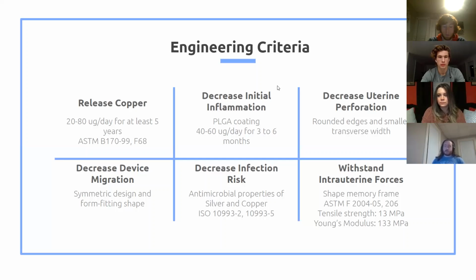So there are 6 main criteria that our device must meet. It must release copper at a known and controllable rate for the IUD to function as a contraceptive. It must reduce the amount of initial inflammation, which is tackled with the PLGA coating we put on there. It must decrease the rate of uterine perforation with rounded edges and a less aggressive shape.